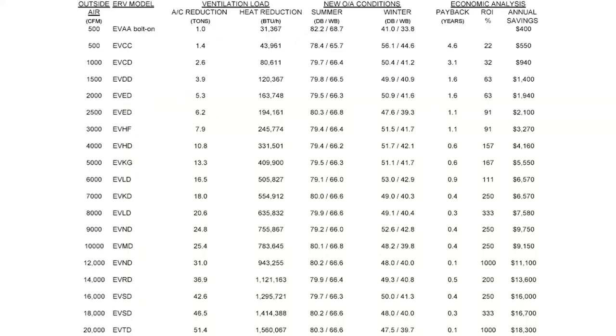Paybacks can be pretty quick. This chart is specific to rooftop replacements. Other scenarios would be a little bit different, but this gives you a general idea. If I take an example here with 1500 CFM of outside air, and I picked a specific wheel model number, in this case it is reducing my cooling needs by 4 tons. If I was in the market to get an 18 ton rooftop unit, I am now in the market for a 14 ton rooftop unit, because 4 tons is getting done for me before it even gets there. And I'm going to look for something with 120,000 BTUs less of heat.